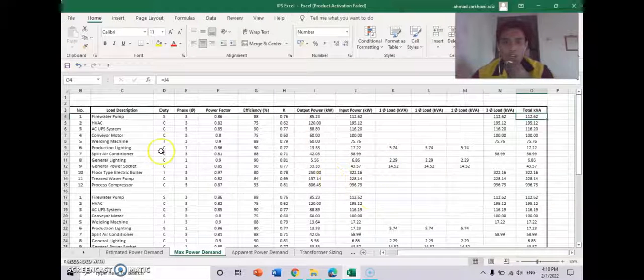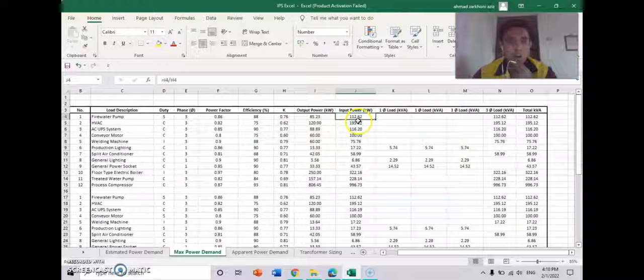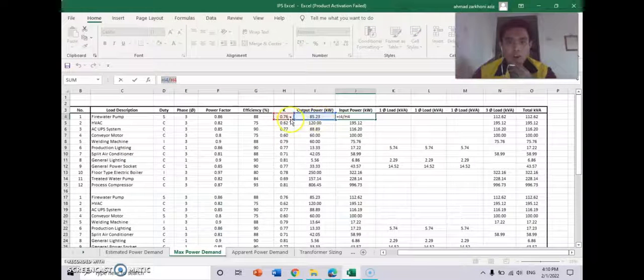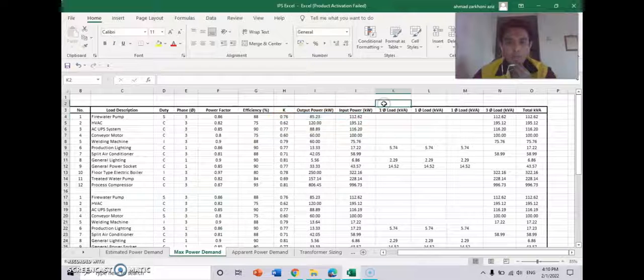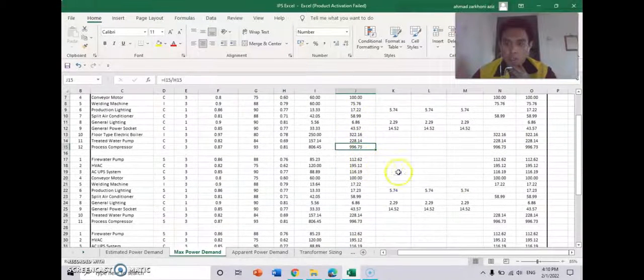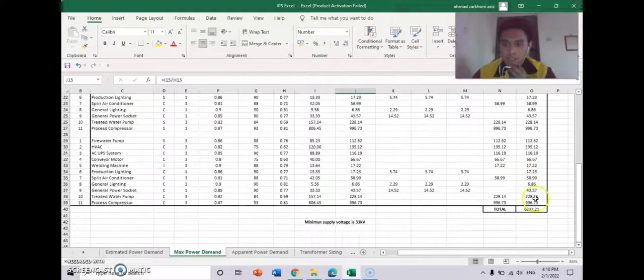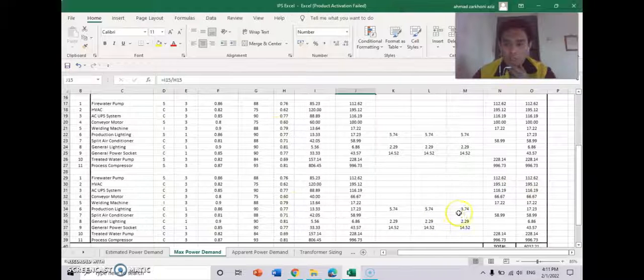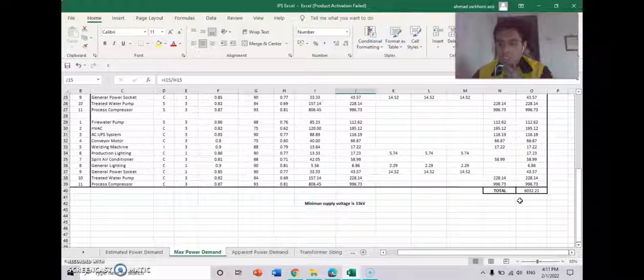For maximum power demand, how do we calculate the input power? We use I4 over H4, where I4 is the output power over K: 85.23 over 0.76. So we will get 112.62. This will be in total kVA. For input power, we use the same formula for all, and from the input power we will get the total kVA. So the total amount of kVA for all of the loads is 6,032.21 kVA.